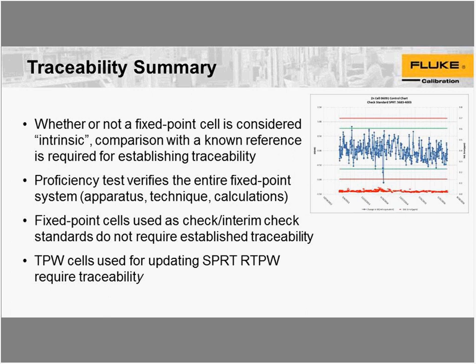Maybe this is where you will need the best uncertainty available, and you may have to send it to NIST, but you can also send it to a laboratory that provides certification or intercomparison services for fixed point cells. But you can also do intercomparison yourself.